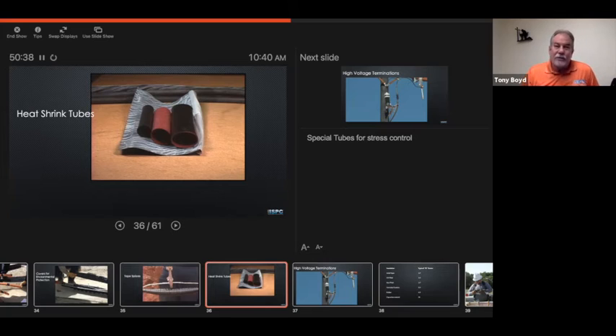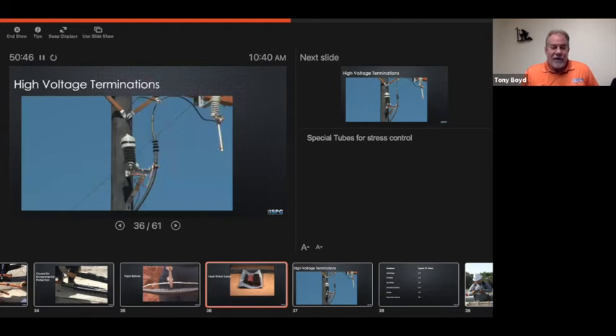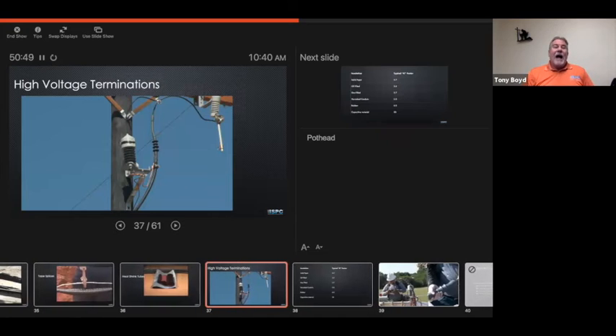These are all heat shrink tubes, and you should always use the proper heat to shrink them, and make sure that you use it properly, know how to use that kind of thing. All right, high voltage terminations. This is what we call a pothead. The reason it's called a pothead is back in the 60s and 70s, when these terminators were put together, it was actually a large porcelain pot. So you would make up the cable, stick it into the pot, pour some resin in there to evenly allow the stress around it. So that's why you got the term pothead, and it just stuck.